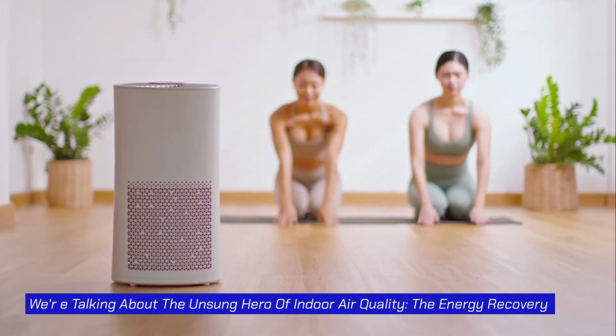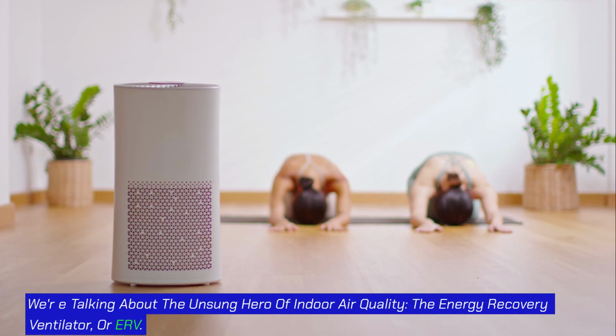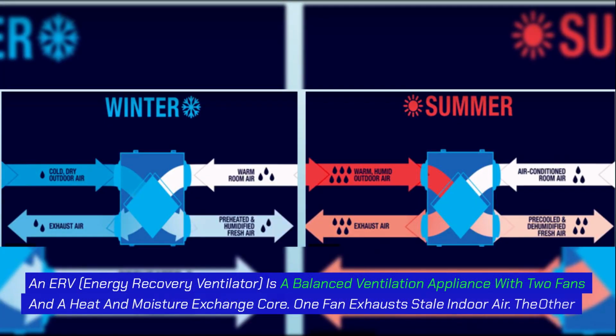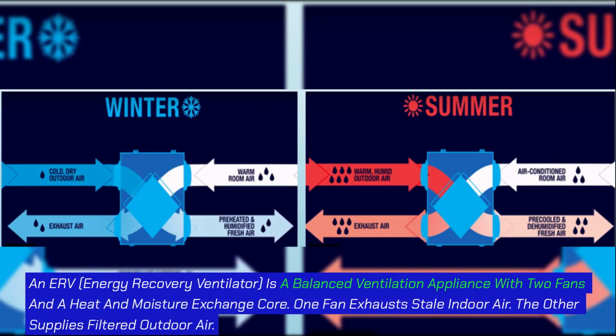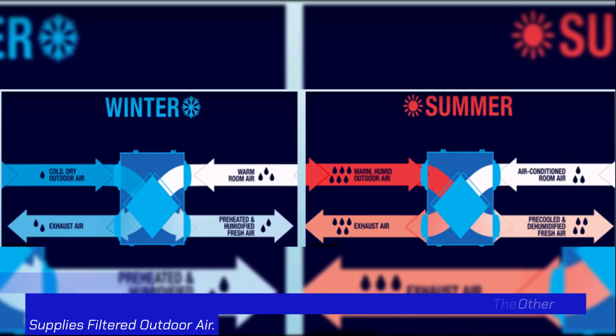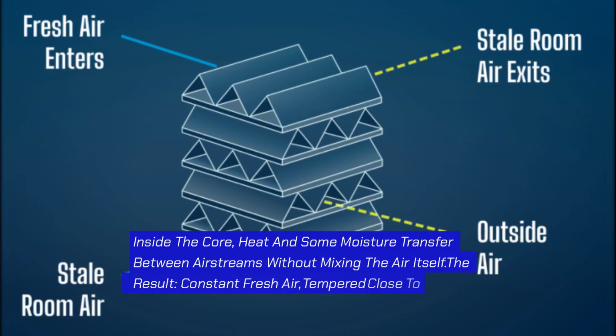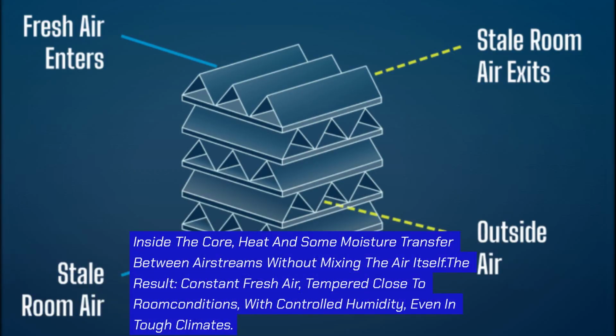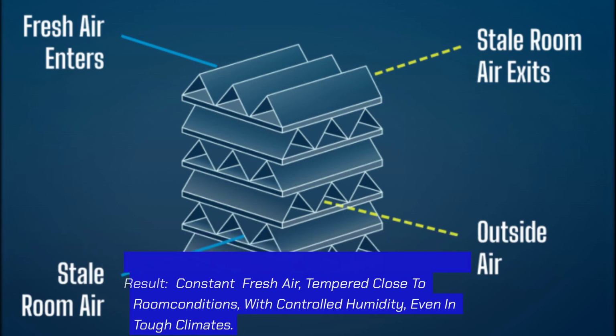We're talking about the unsung hero of indoor air quality, the Energy Recovery Ventilator, or ERV. What is an ERV? An ERV, Energy Recovery Ventilator, is a balanced ventilation appliance with two fans and a heat and moisture exchange core. One fan exhausts stale indoor air. The other supplies filtered outdoor air. Inside the core, heat and some moisture transfer between airstreams without mixing the air itself. The result: constant fresh air, tempered close to room conditions, with controlled humidity, even in tough climates.